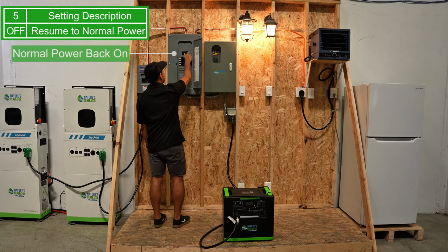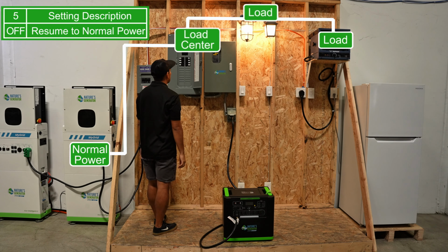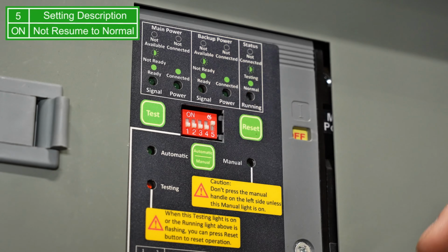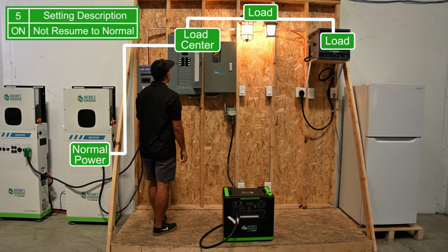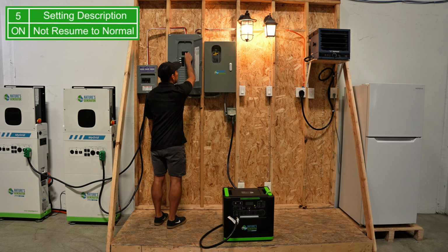First, we set the switch to off, and the ATS resumes normal power when it's ready. Now, we switch it on, and the ATS remains on backup power despite normal power being available.